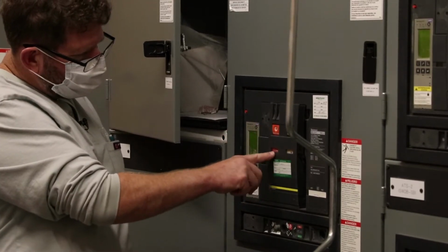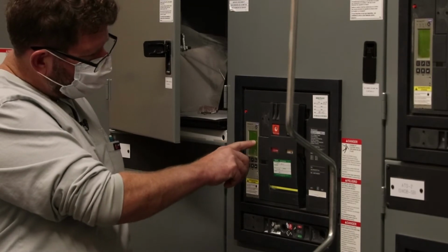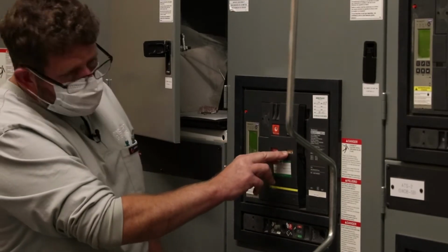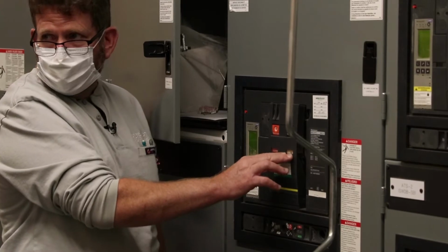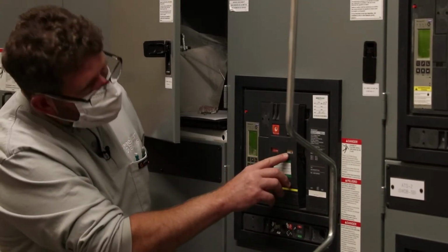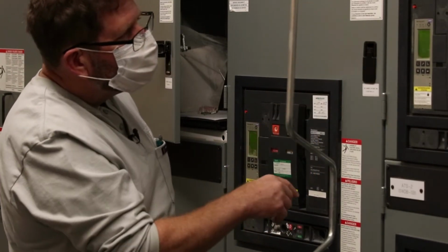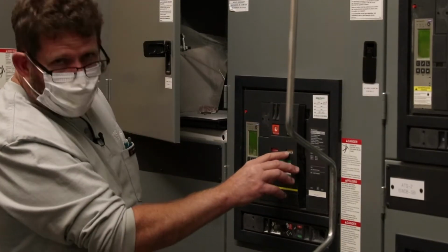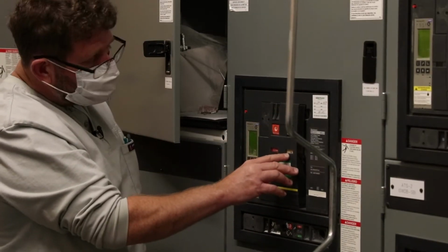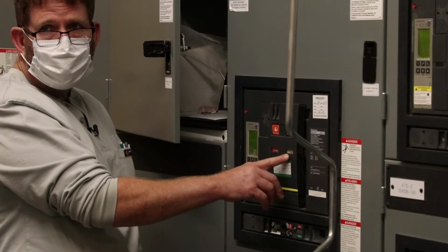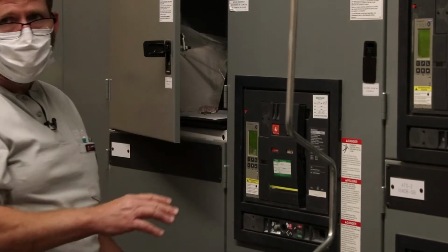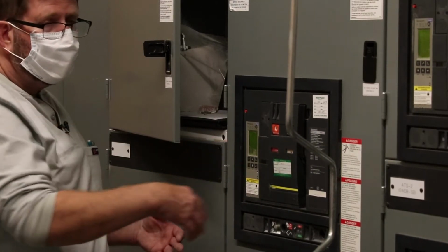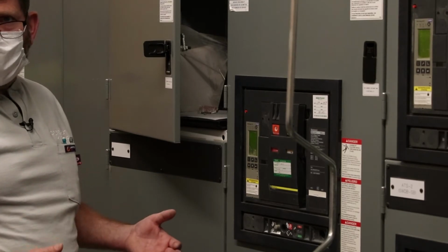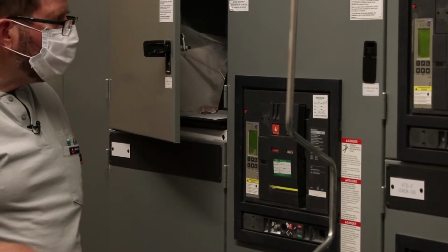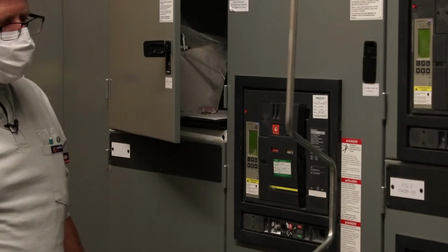You operate the breaker, open and close, right here. Right now you can see it's closed. You're carrying 240 amps load. Right here in this flag, this is your spring charging indication. If you look, all the breakers that are closed have a little yellow flag that says charged, but it also says not okay. What that means is it's not okay to close right now. In this case, it's not okay to close because it's already closed.